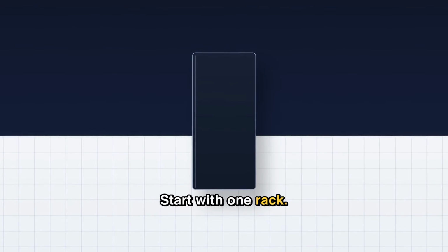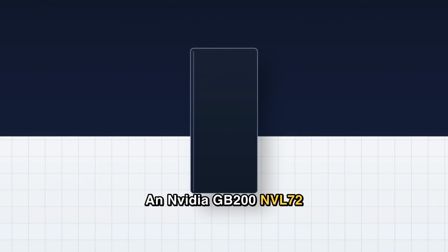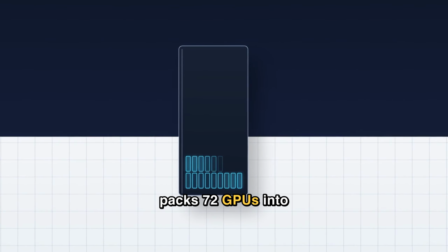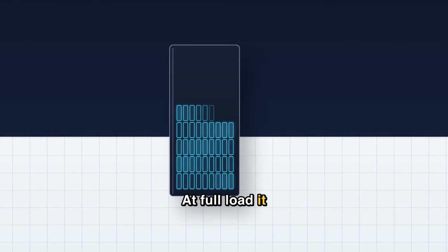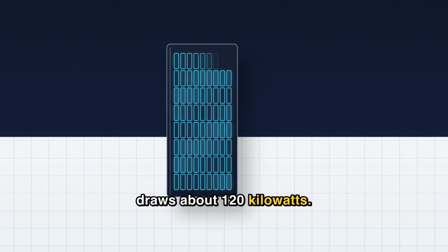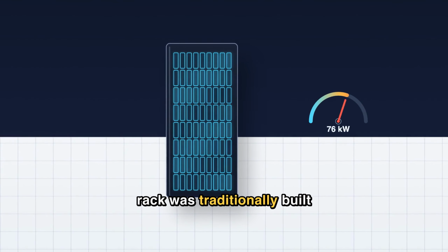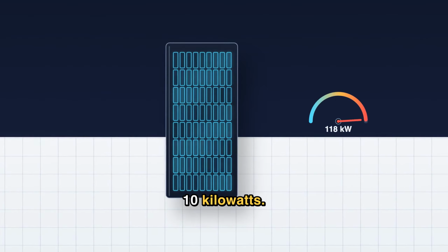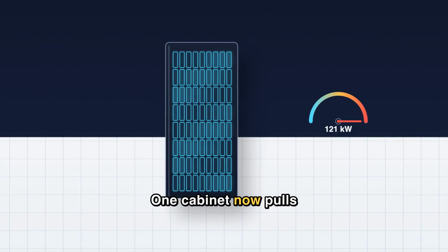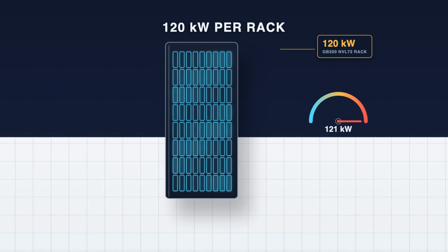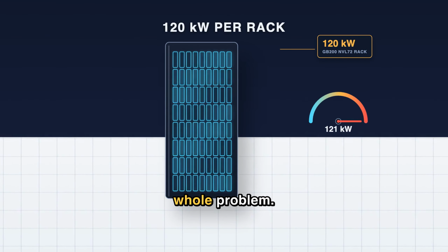Start with one rack. An NVIDIA GB200 NVL72 packs 72 GPUs into a single cabinet. At full load, it draws about 120 kilowatts. Here's the shock: a rack was traditionally built for just 3 to 10 kilowatts. That's the jump. One cabinet now pulls the power of a small neighborhood. This single rack leap is the root of the whole problem.